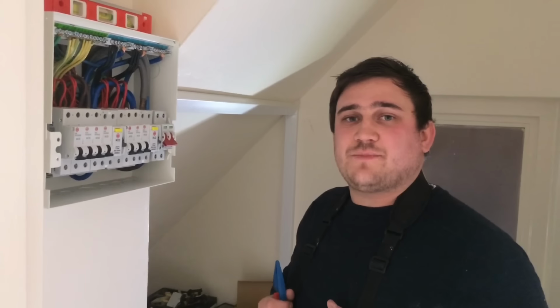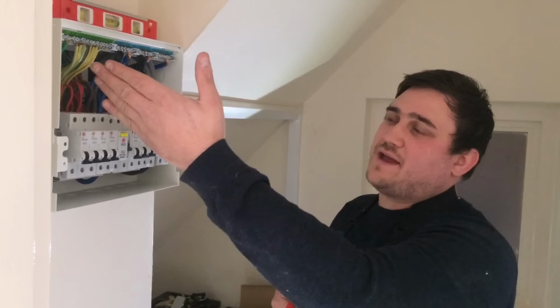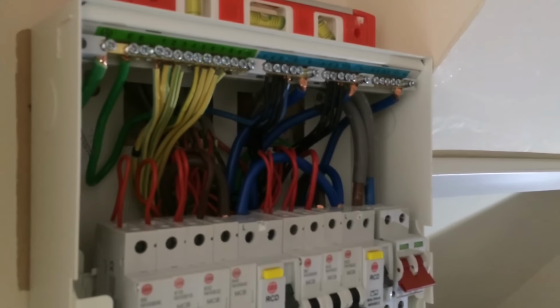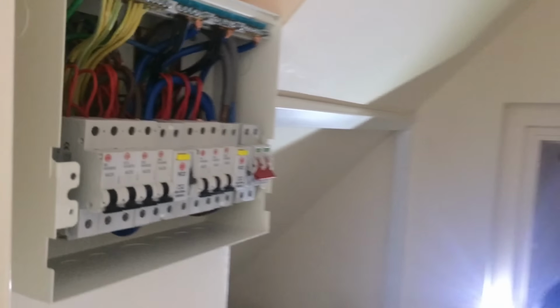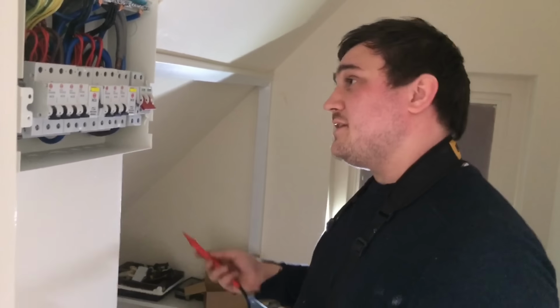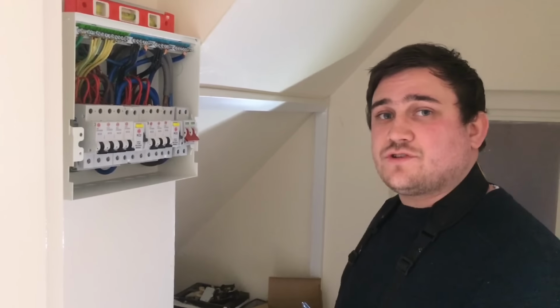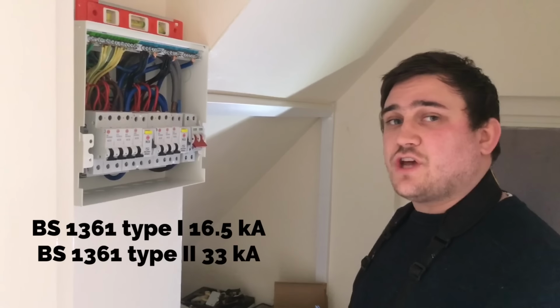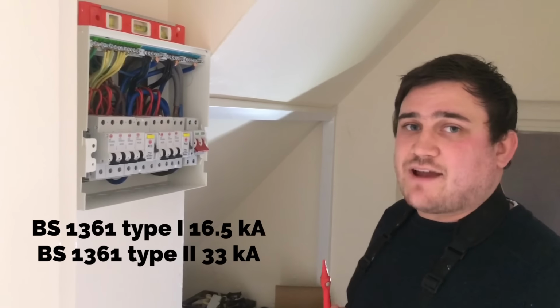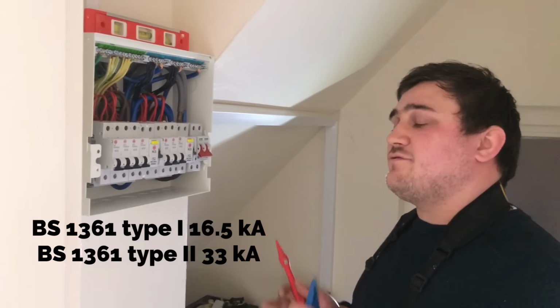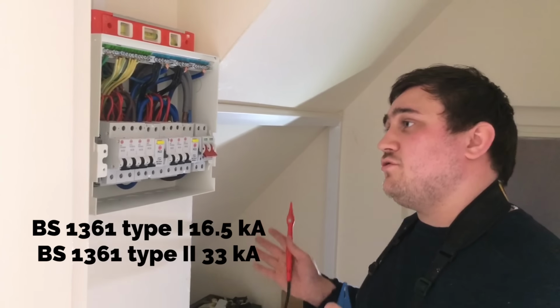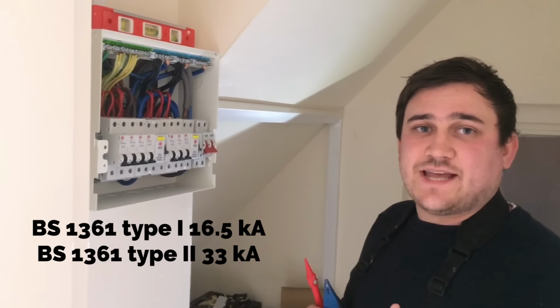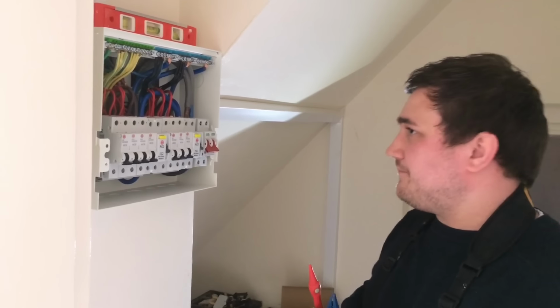We're now carrying out our prospective fault current test. For this we put the main earthing conductor back in the board. This is because we now want to take into consideration the parallel earth paths. First of all, we're going to check again the PFC against the main incoming fuse. It's rated at 60 amps. However, we looked on the side, there is no breaking capacity rating. However, we do know they range from 16 kiloamps to 33 kiloamps. We're going to take it from the lowest end, the worst case scenario.